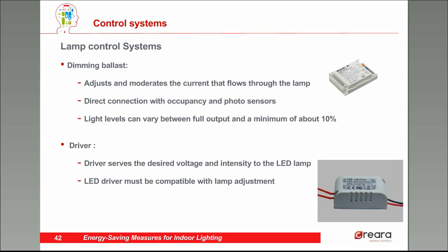These control systems read the variables and act in response. The detectors — occupancy or sunlight — read the inputs and send a signal. But the lamp's power needs to be adjusted, so we require, apart from the detectors, a special auxiliary equipment that has to be compatible with the adjustment. For fluorescent lamps, we have the dimming ballast. And for LEDs, we have the driver — the driver must be compatible with lamp adjustment.